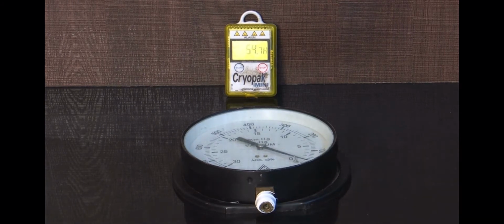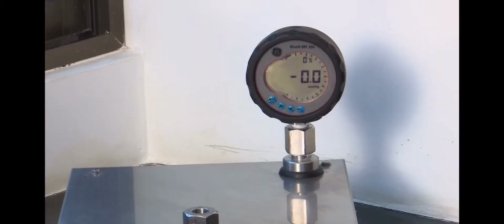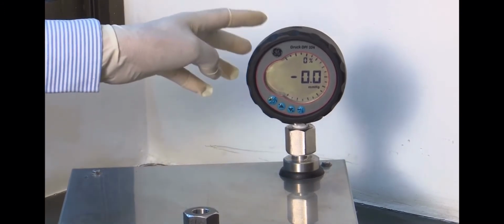Before starting calibration, ensure that the environment condition is maintained. The temperature should be between 23 plus minus 1.5 degrees centigrade and humidity should be 40 to 60% RH. For calibration, we will use digital pressure gauge.